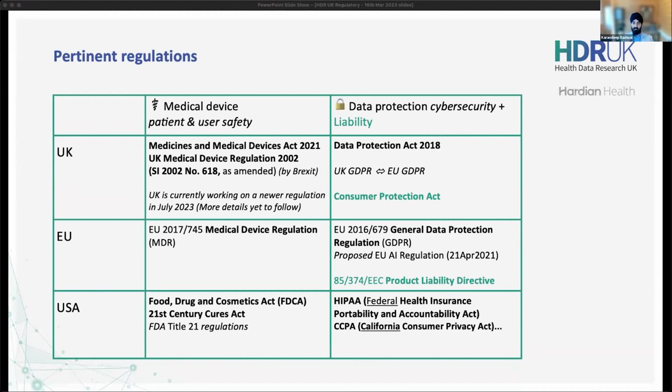So there's two sides of it because we're talking about software here. There's the medical device regulations that you have. We've also got things like data protection and cybersecurity because using software, these things are connected to online systems, etc. So there's two different considerations here. And of course, in the UK, we have the UK Medical Device Regulation, UK MDR 2002. That is effectively a carbon copy, more or less, of the old EU Medical Device Directive.